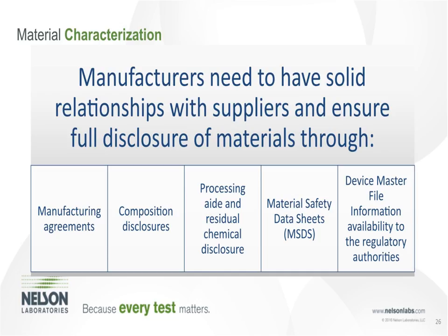Yes, but not all silicones are the same. Not all polypropylenes are the same. They have different stabilizers, different additives, and so the toxicities can vary quite a bit between different types of silicones and materials. So just because it says that it's a silicone, it doesn't mean that you're done. You really have to know what is in it, and if that requires chemistry to do so, so be it.